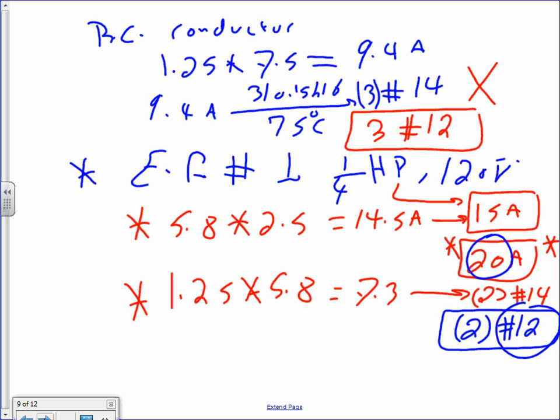Okay, here's another example. That's not good enough for you. Exhaust fan. I have one exhaust fan, number 1, it's a quarter horsepower, 120 volts. If you go to the NEC code book, the full load current of that one is 5.8. Multiplied by 2.5, gives you 14.5 amps. I end up with a 15 amp circuit breaker, and you calculate, this is single phase.